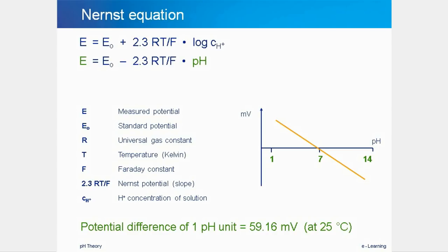The Nernst equation consists of several physical constants and the temperature of sample and electrode. If all physical constants and a standard temperature of 25 degrees Celsius are input into the equation, the relationship between potential and pH is a potential change of minus 59.16 millivolts per pH unit. So if the pH value increases from 7 to 8, the potential decreases from 0 millivolts to minus 59.16 millivolts. This well-defined relationship between potential and pH enables us to measure the pH value and calculate the concentration of acid or base present in the sample.